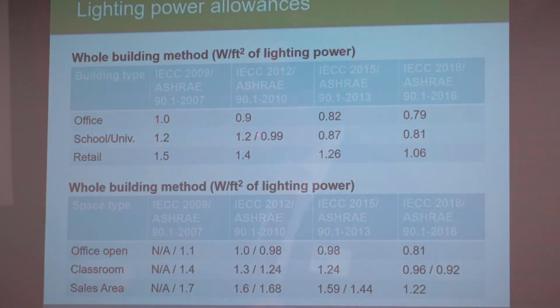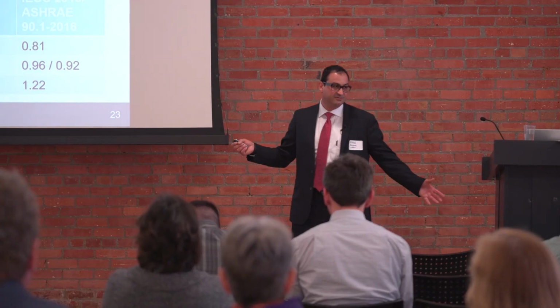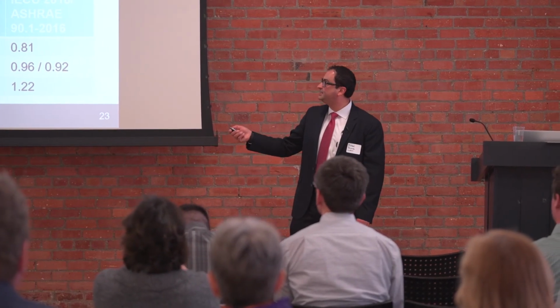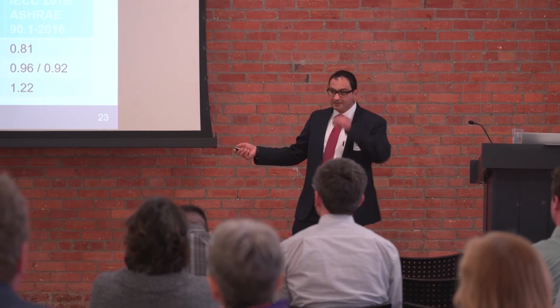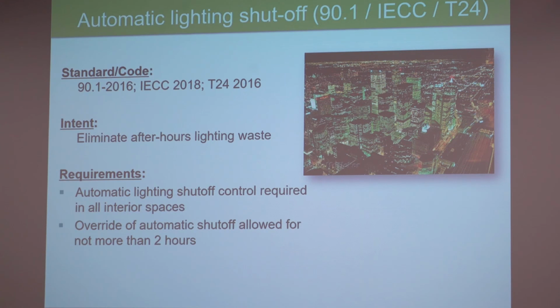Here's a slide that shows the lower lighting power densities of each of these standards. Most of the time, the IECC and ASHRAE 90.1 lighting power densities, or watts per square foot of lighting power that you can use in your buildings, are the same. Occasionally, IECC and ASHRAE differed. But the point I really want to get across here is these lighting power densities have gotten lower each time they do a new code revision. The top table is the whole building method. The bottom is the space-by-space method. That was the lighting requirements: meet those watts per square foot numbers.